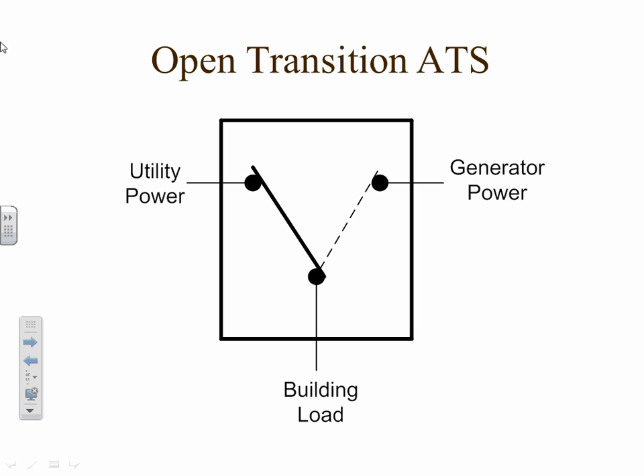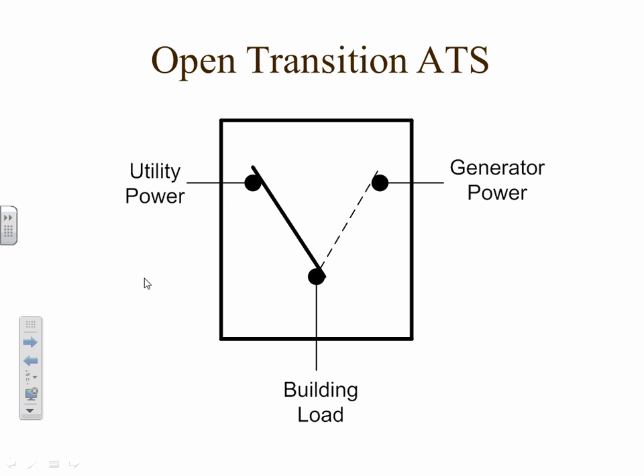Before I move on, though, I'm going to describe that there are 4 time delays in every transfer switch, and I'll describe what they're for. This drawing is a good one to do it on. There are 4 time delays in every switch of every type that I'm going to show you. The reason they exist, if we take a day like today in Minnesota, we've just had some ice and some snow. That might be on the power lines outside, some smaller towns out down distribution ways. Now we've got a tree sitting close to that power line, and that might be just bumping it enough to be causing a problem with power someplace, and then it's just blinking off and on.